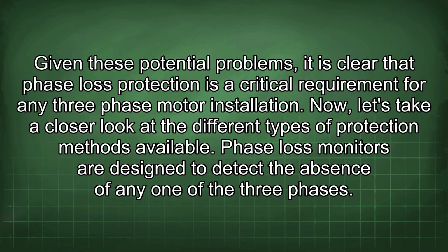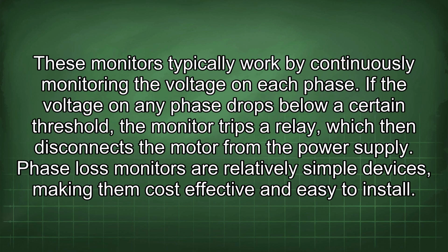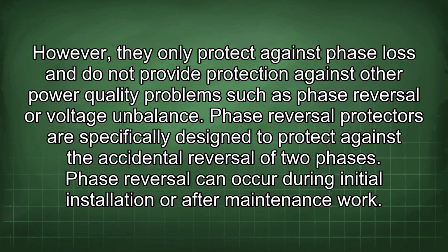Phase loss monitors are designed to detect the absence of any one of the three phases. These monitors typically work by continuously monitoring the voltage on each phase. If the voltage on any phase drops below a certain threshold, the monitor trips a relay which then disconnects the motor from the power supply. Phase loss monitors are relatively simple devices, making them cost-effective and easy to install.